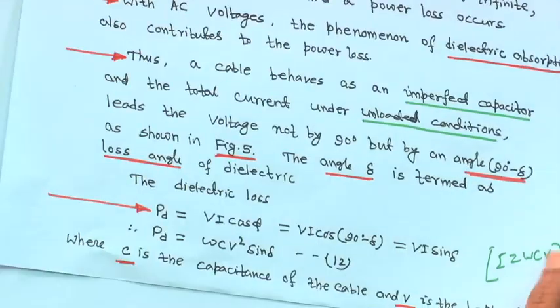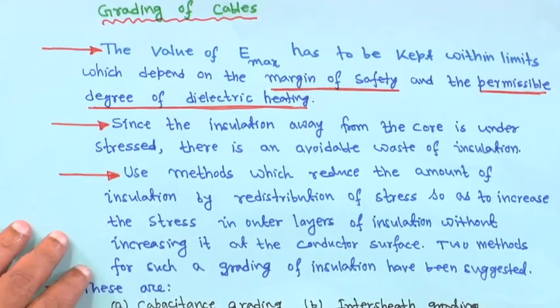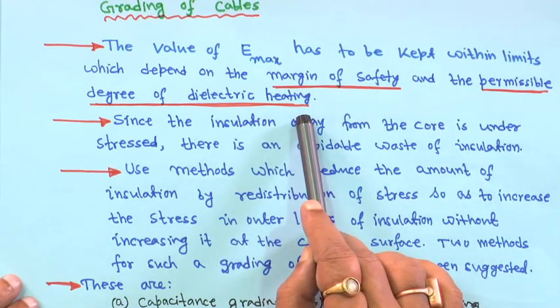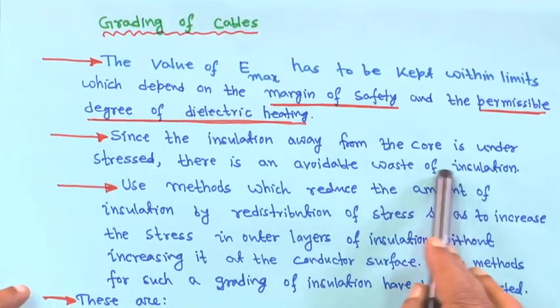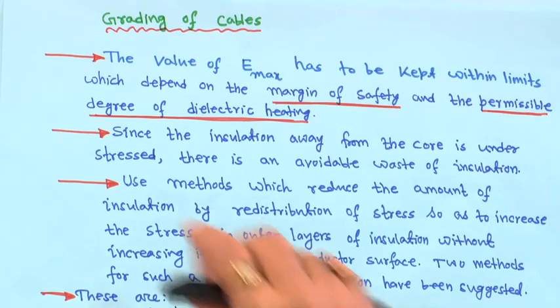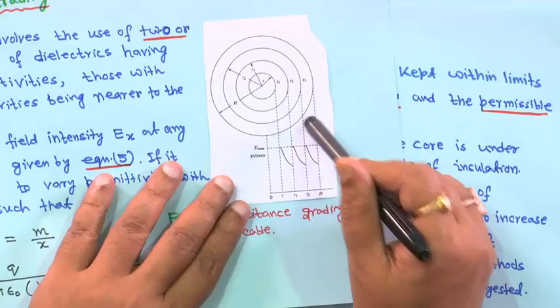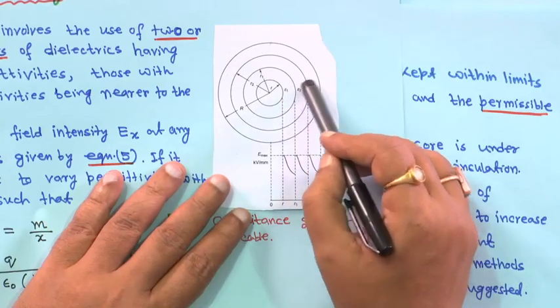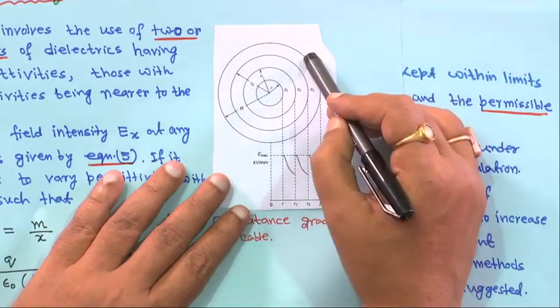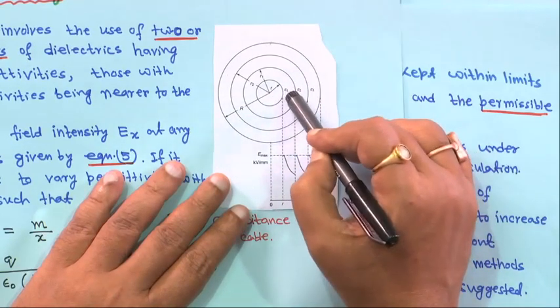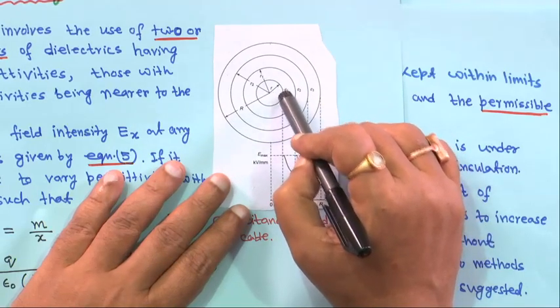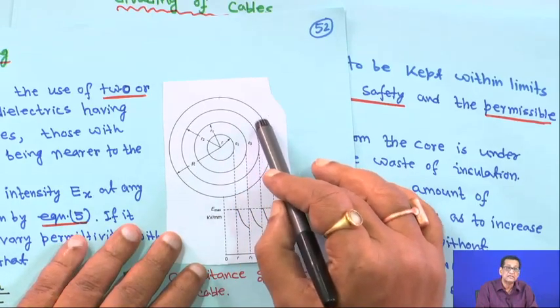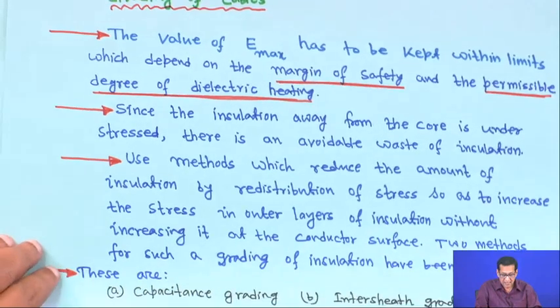Next we consider the grading of cables, because the value of E_max has to be kept within limits which depend on the margin of safety and the permissible degree of dielectric heating. The insulation away from the core is under-stressed, while insulation very close to the core conductor is over-stressed.